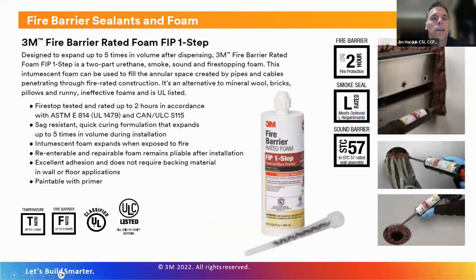The next product I want to discuss here is our FIP foam. This is a 2-component urethane foam. So basically, when this material is dispensed, it expands about 5 times in volume. It's a great product to use for applications where you have limited access, or if you have a group of cables that are tightly bundled together because of the expansive nature of the material. It kind of fills all the voids very well. We have tested systems with this product for up to 2 hours. This is a 2-component material, so it does require a special application tool. We have a pneumatic dispensing gun that we use, and it gets dispensed through a static mixing tube.